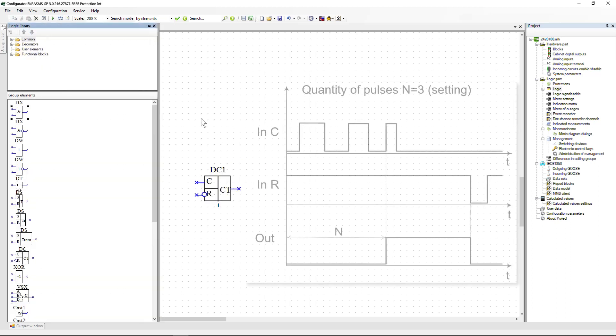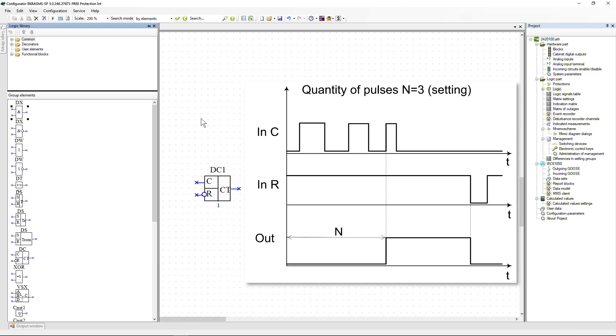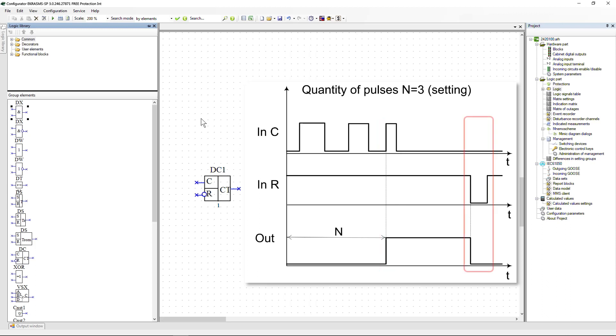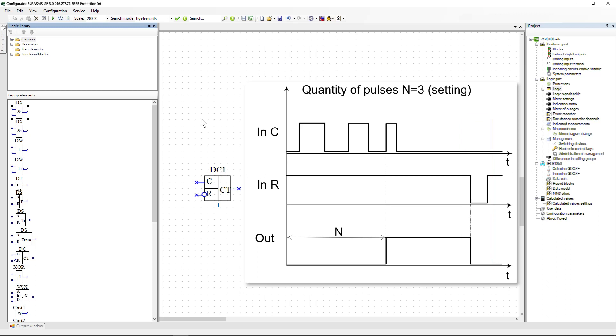Pulse counter (P): counts the pulses received at input C. When the number of pulses specified by the setting is exceeded, a logical one is latched at the output of the counter. The output signal is reset by generating a signal at the R input. If the signal at input R is generated before reaching the operate setting, the counted number of pulses is reset and counting starts again. Note that by default this input is inverted; if necessary, the input mode can be changed.